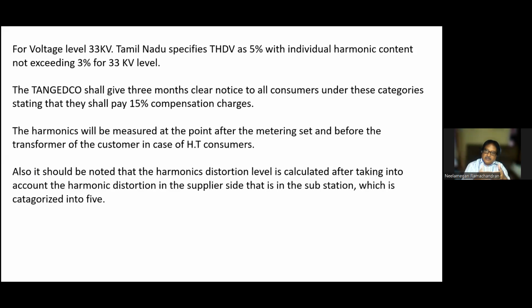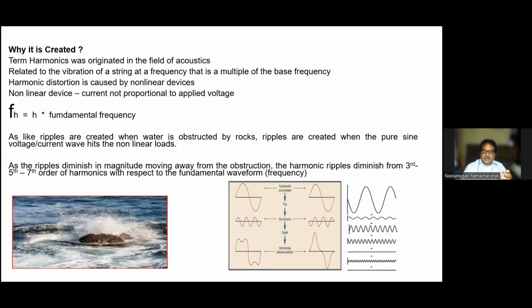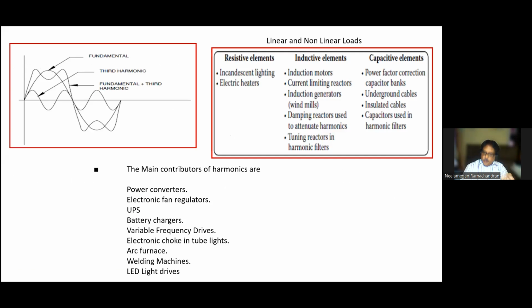So by extending all these things, putting your VFD drive, putting LED bulbs, I have listed the things: electronic fan regulators, UPS, battery chargers, variable frequency drives, electronic choke tube lights, arc furnace. These are all the main gadgets that produce harmonics, and be assured these will not be affected at all. The instruments or machinery connected downstream or upstream of these are going to be affected. So as maintenance engineers, we won't have a clue why this accident or breakdown is happening. The culprit will be sitting coolly somewhere, working very well without any problem, but producing harmonics.